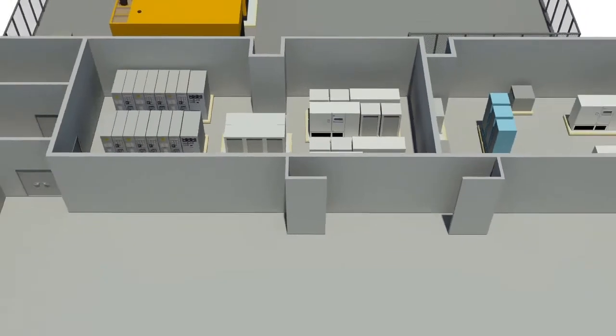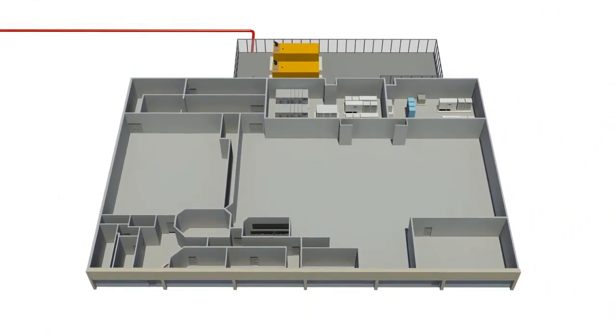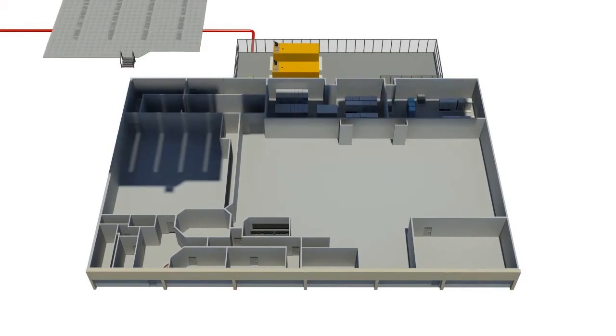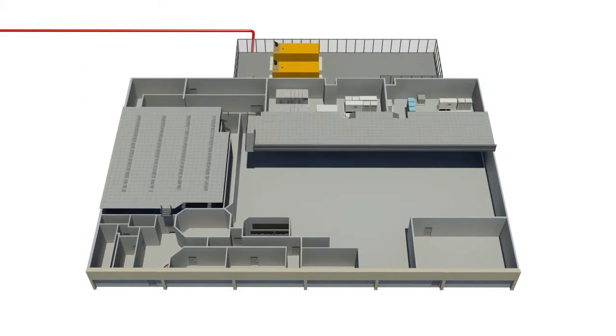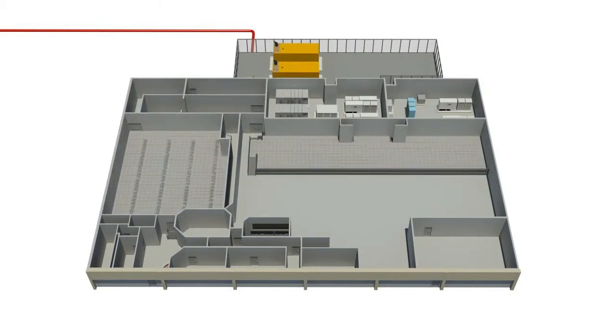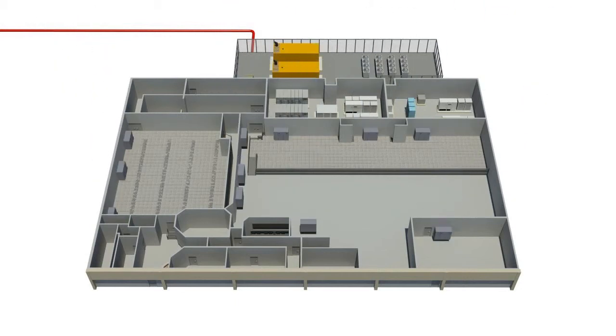The inside of the data center is intricately engineered to provide an optimal operating temperature at all times. 6,200 square feet of the total 21,000 square feet facility are engineered with raised floor space. This system circulates cool, temperature-controlled air into the server rooms through floor-level ventilation systems. 14 redundant high-capacity computer room air conditioner units producing 540 tons of cooling are positioned throughout the facility.